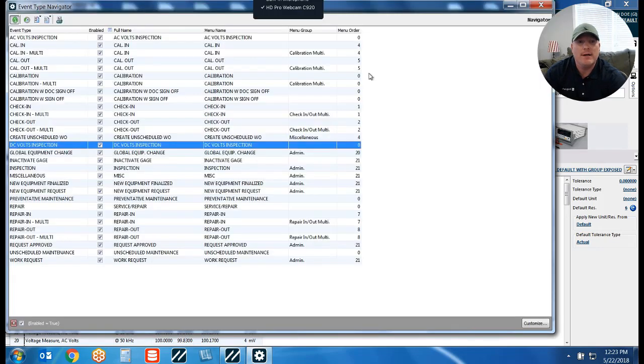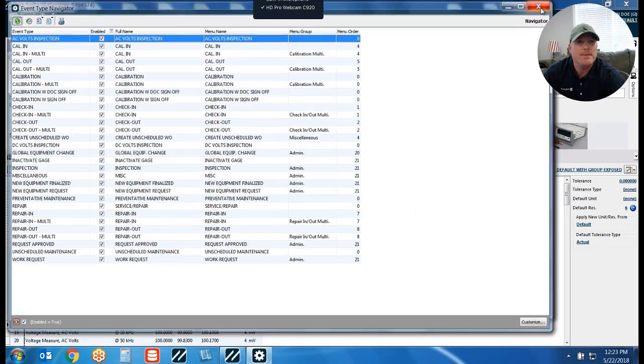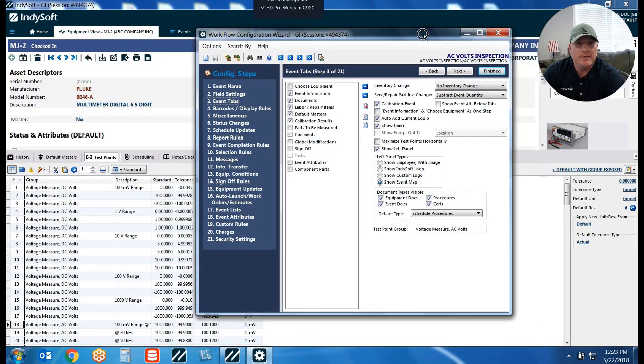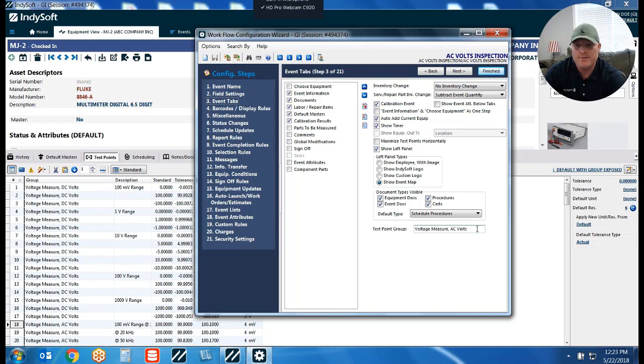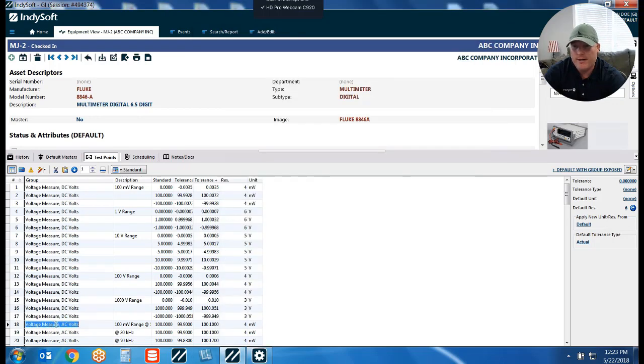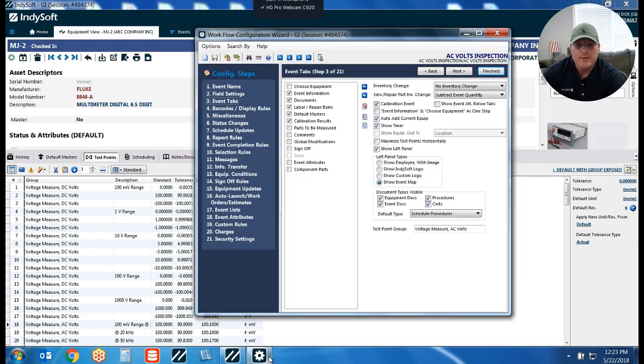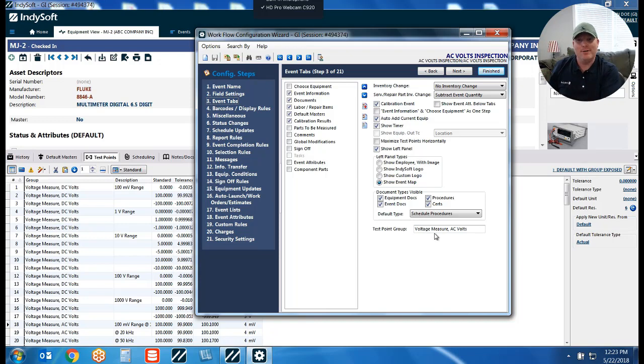If I look at my AC Volts Inspection event, in step three my test point group is declared as 'Voltage Measure, AC Volts' — which is a direct match of what is specified on the equipment view. So essentially what you want to do is set up your test point group to match the group you set up on the equipment view, if you want an event to pull in a specific set of test points.